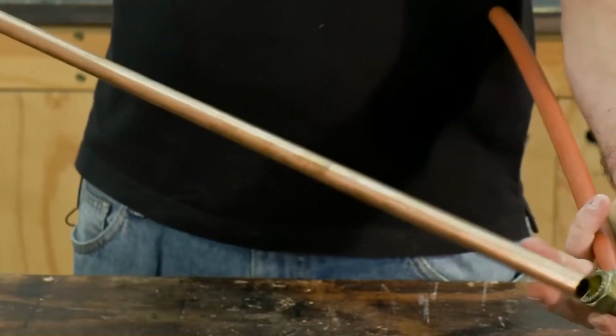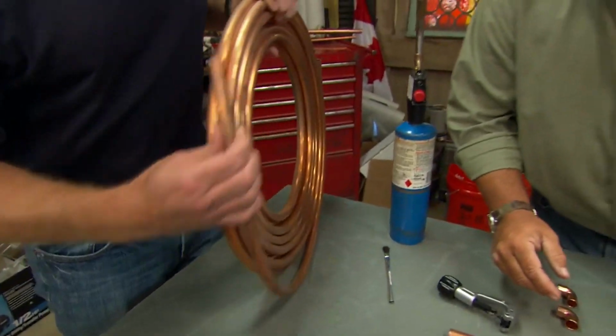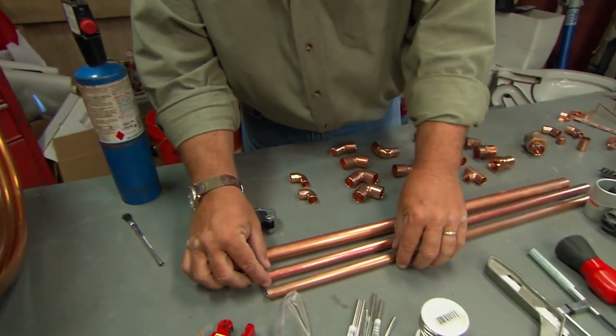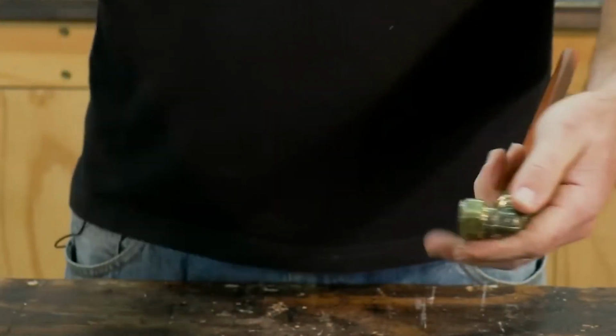Absolutely. You can adapt and transition piping, with the exception of black steel, in a water system pretty much any way, shape, or form. So if you have a copper system and we need to make a repair or cut out a 10-foot section and replace it, it's very common to go from copper, replace that section with PEX, then back to copper. Again, due to pricing and durability, it's just as good, if not better, of a repair doing it that way.